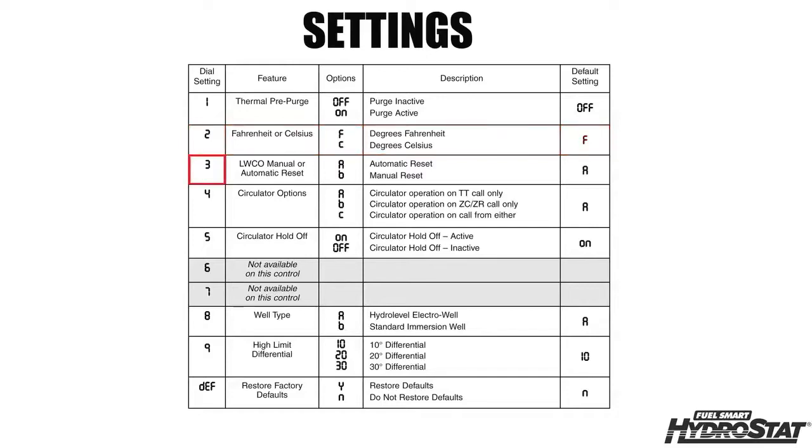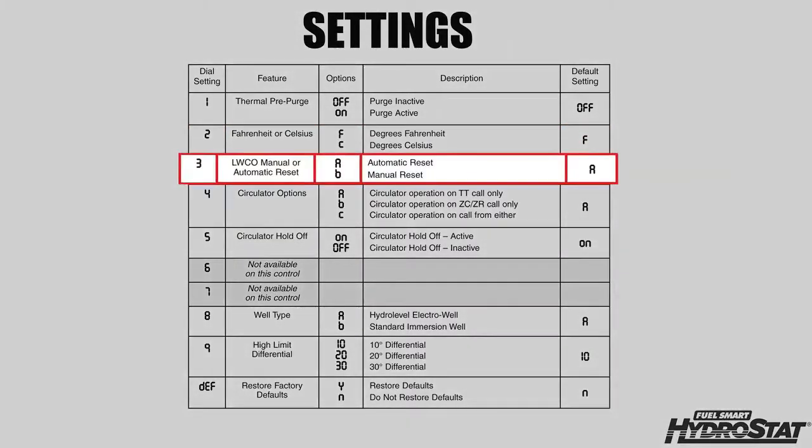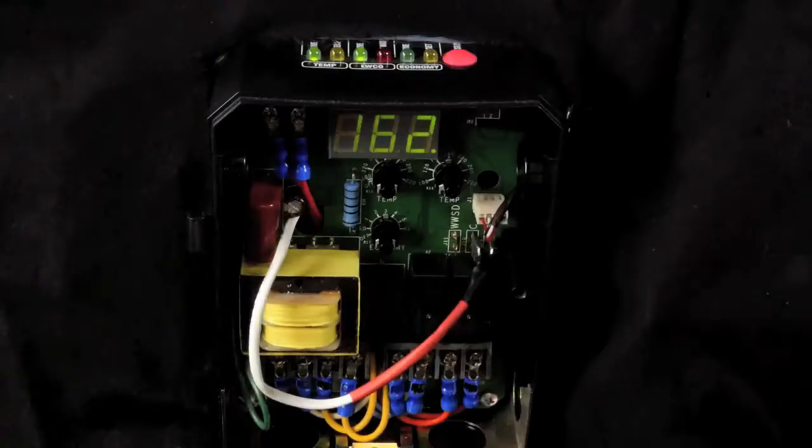Option three enables you to change the operation of the low water cutoff to function as a manual reset control. This can be a useful feature if the boiler is installed in a commercial building that may require a manual reset low water cutoff.